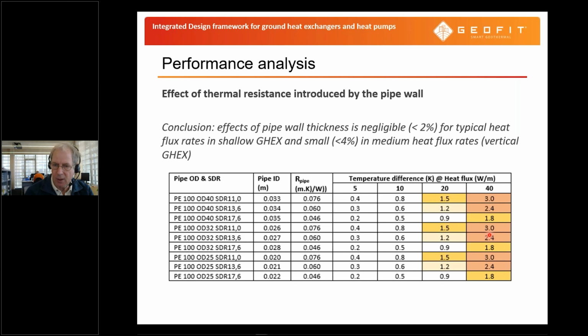And what you can see is that only in situations with a high flux rate, higher than 20 and approaching 40 watts per meter and relatively thick walls with SDR11, it becomes an issue, and you could think about using other materials to achieve a better performance. But in any case, the total effect is on the order of 4% in medium heat flux rates for vertical boreholes, and in shallow heat exchangers, it is even smaller because, as I've explained before, the thermal resistance is smaller even at low Reynolds numbers in helical type of situations, and we have an effect that is on the order of 2% or less. So this gives an indication how important the wall characteristics are in a heat exchanger.